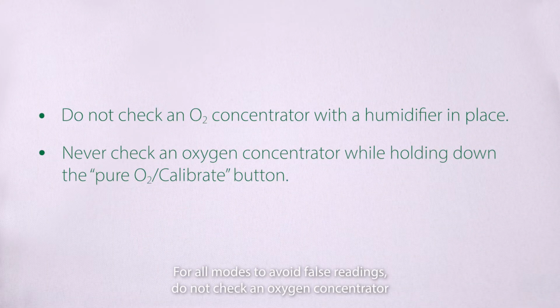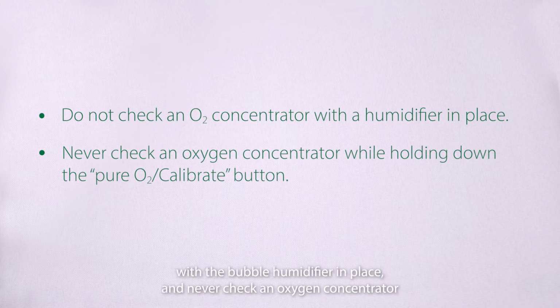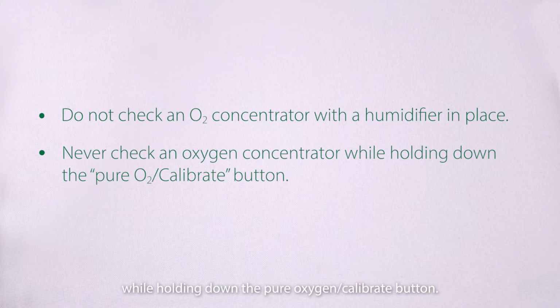For all modes, to avoid false readings, do not check an oxygen concentrator with the bubble humidifier in place, and never check an oxygen concentrator while holding down the Pure Oxygen Calibrate button.